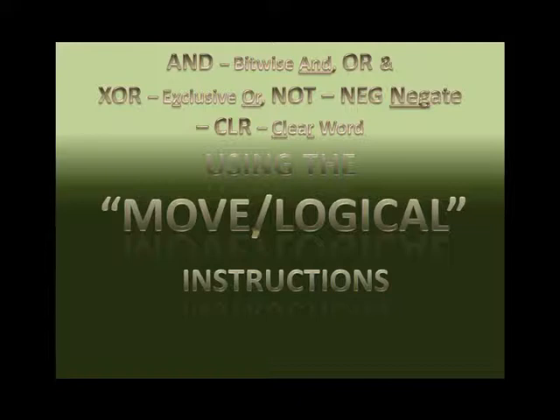The OR instruction will put a 1 in the destination bit position if either one of the two bit positions of the other two words are 1. Whereas the Exclusive OR will set the destination to 1 if either one of the two sources are 1, but not both of them. If they're both 1, because it's exclusively OR, it will not set the destination to 1.